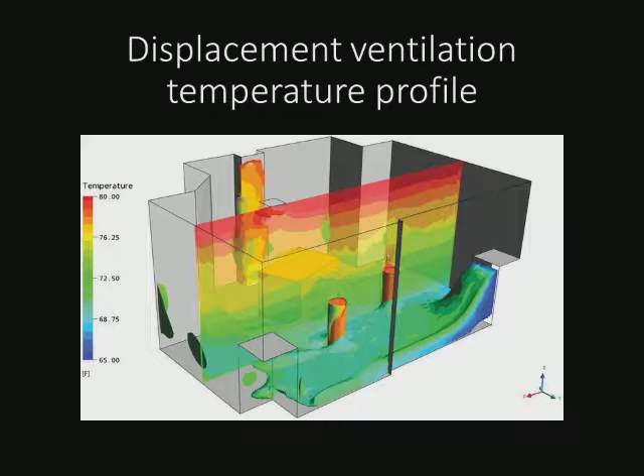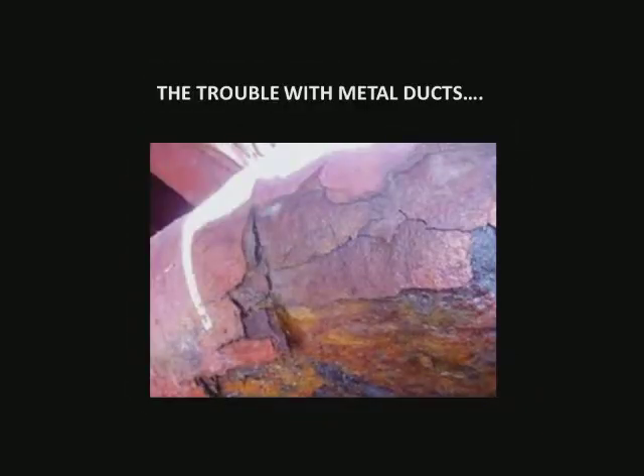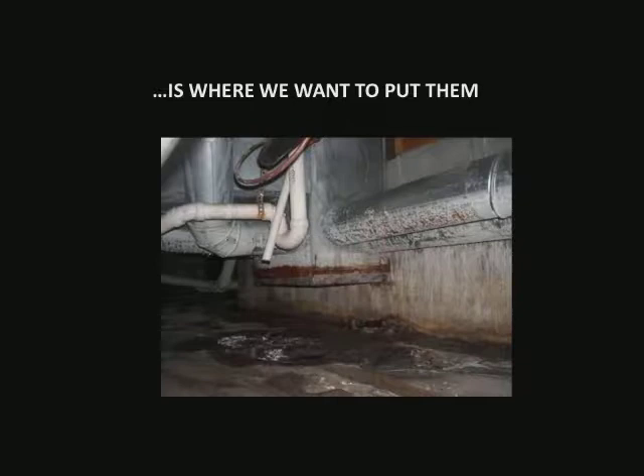Now, because we're transitioning to underground ductwork with displacement ventilation, we need to look at duct materials other than sheet metal. Everyone's pretty familiar with the fact that if you put sheet metal underground, you're going to have nothing but corrosion trouble. That being said, with fiberglass coming into the marketplace, there's a lot of learning to be done by a lot of contractors out there.